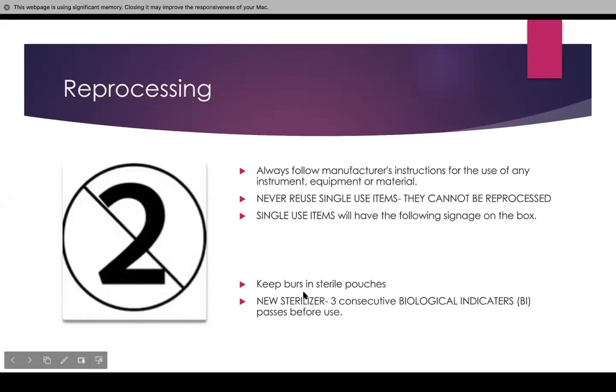You have to keep burrs in sterile pouches and new sterilizers. For every office that obtains a new sterilizer, you have to have three consecutive biological indicators that pass before use. That means you cannot put in your first cycle before creating three biological indicators that are negative — showing no spores growing.